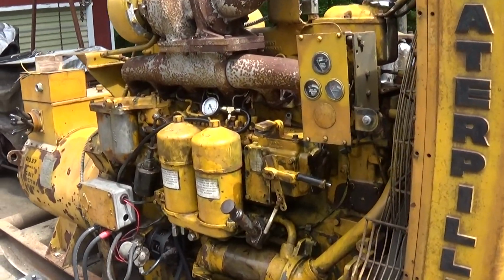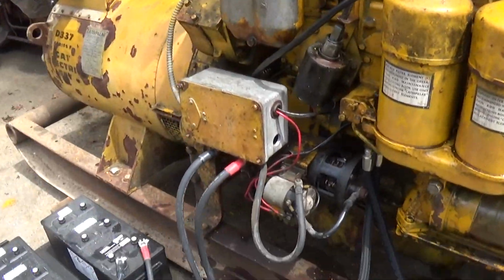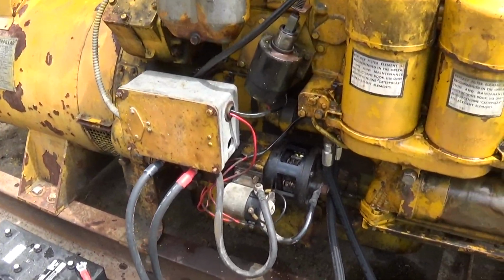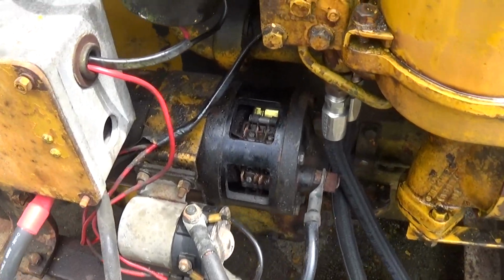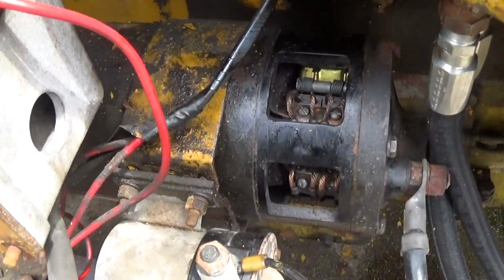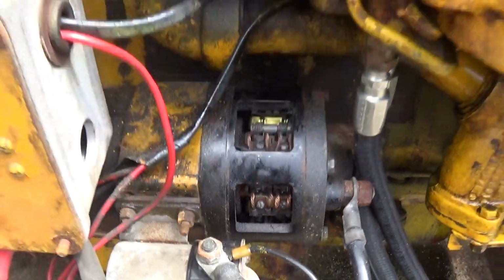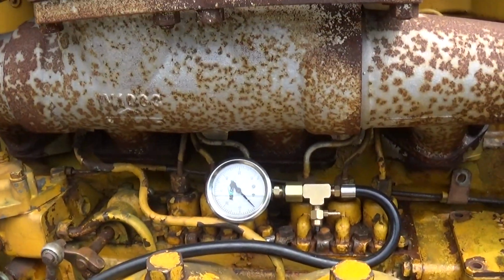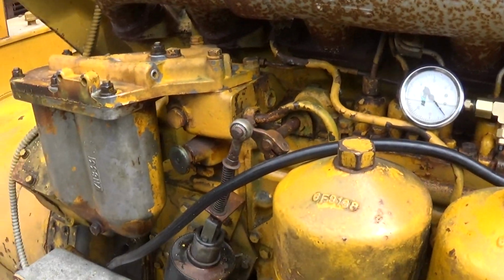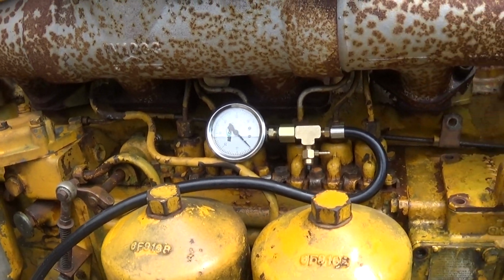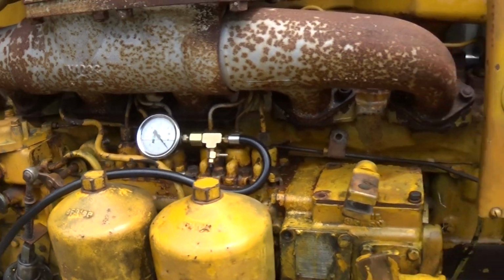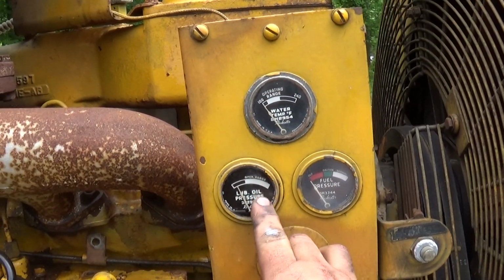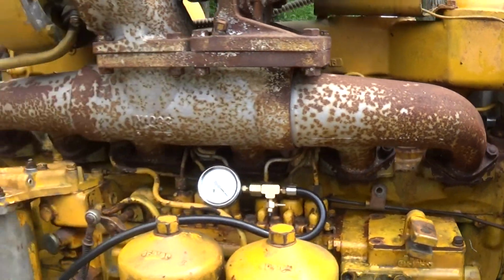Alright, it's time to try to start her up. Fuel's hooked up, batteries are hooked up. Pulled the cover off the starter just to check the brushes, make sure they're all free. It actually looks really nice in there. Got a separate pressure gauge on the oil gallery, the main oil gallery, so we can see what the oil pressure actually is instead of just whether or not it's in the operating range.